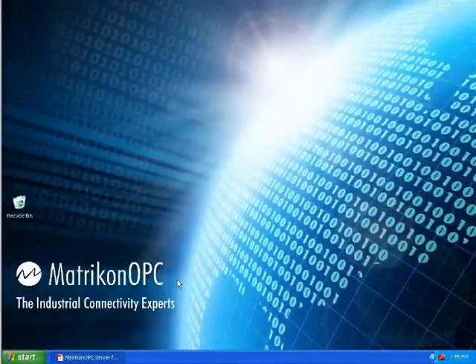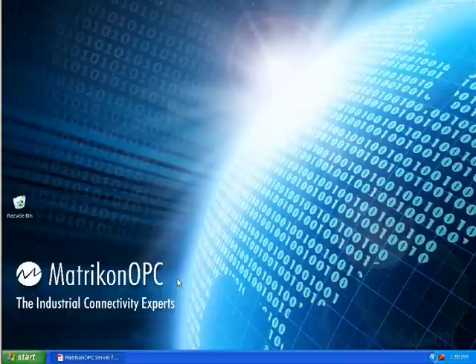Welcome to the configuration guide for the MatrikonOPC Mark 6 Direct server. This server can provide access simultaneously with multiple Mark 6 turbine controllers. To use this server, your machine must be connected to the same unit data highway, or UDH, as the GE Mark 6 controllers. You must also have a copy of the Mark 6 site's configuration file stored on your machine.